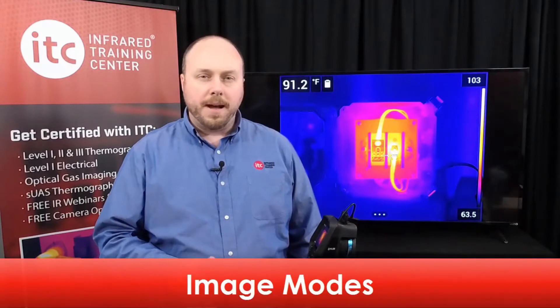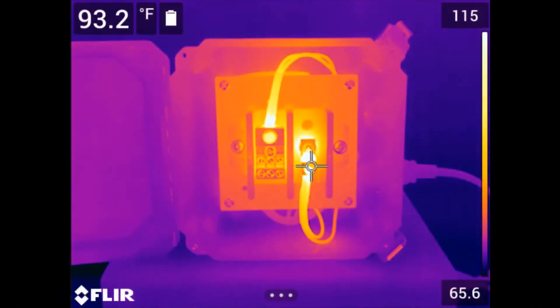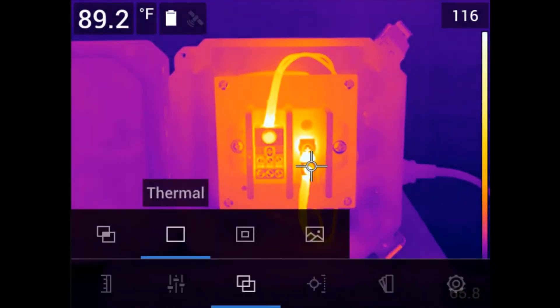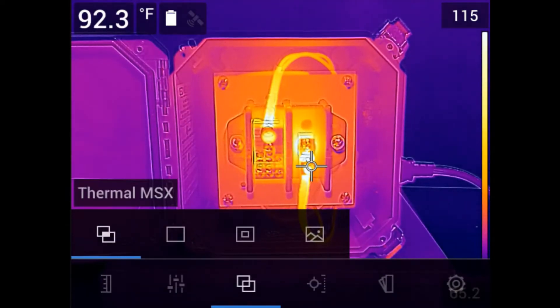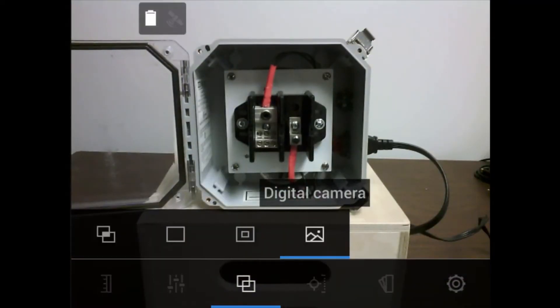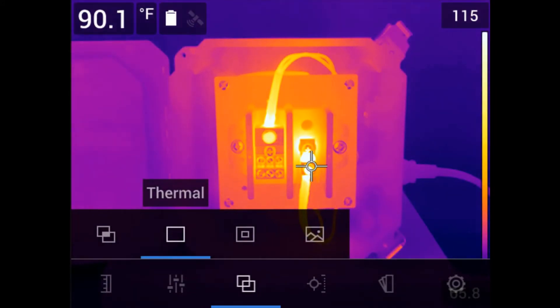There are four different image modes available with this series of camera, accessible via the navigation pad or touch screen. Open the main menu and select the image mode icon. Four options will appear: MSX, which stands for Multispectral Dynamic Imaging; Thermal Only; Picture in Picture; and Digital Camera, which displays just the visible light feed. For those who are new, we recommend staying in Thermal Only mode, as this will help you better understand what's required for proper focus. You can also change the image mode later in the software.